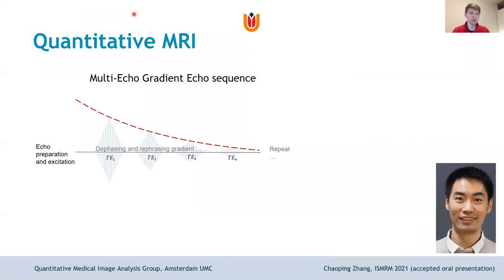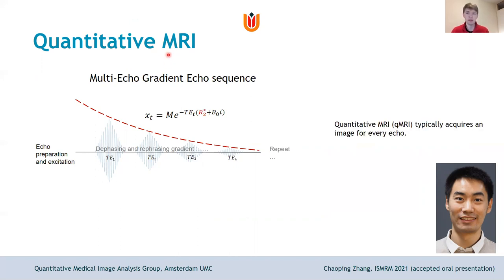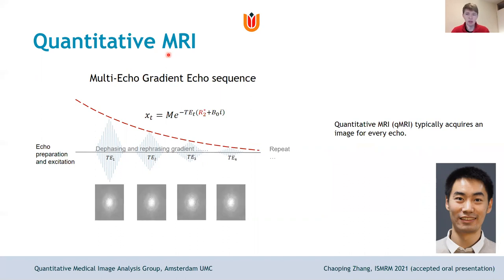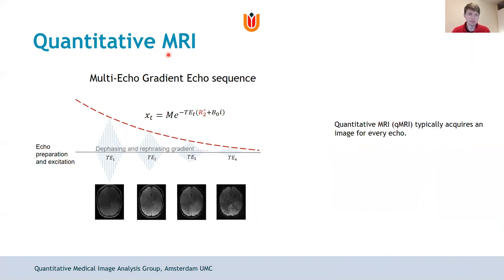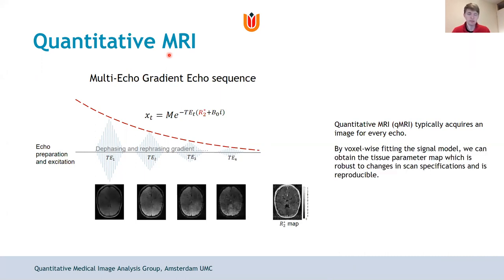The next step is to move to quantitative MRI, focusing on R2* mapping — this is work of Chaoping Zhang in our group. We have a well-known model for R2* over multiple echoes, considering complex-valued signals where the B0 term comes in. Commonly we acquire an image for every echo, do the inverse Fourier transform, and fit a signal model to arrive at our R2* map.